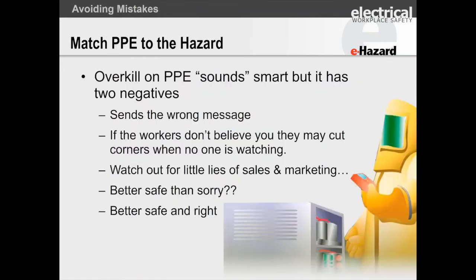Sometimes people say, let's put them in a 100 cal suit because that'll be more protective. The problem is it sounds smart but has two negatives. First, it sends the wrong message—it implies that if you only have an 8 cal exposure, maybe you go for 10 or 12, but not 100 cals, because it makes people think you're afraid or don't understand the hazard.